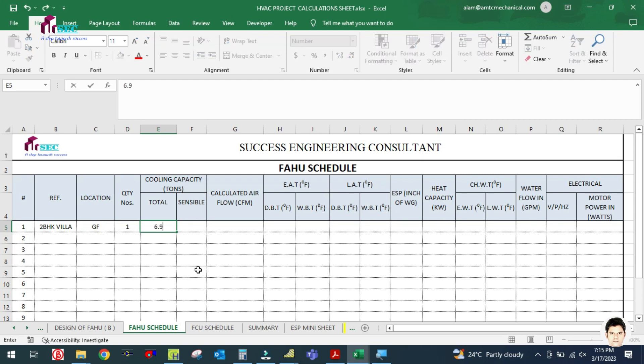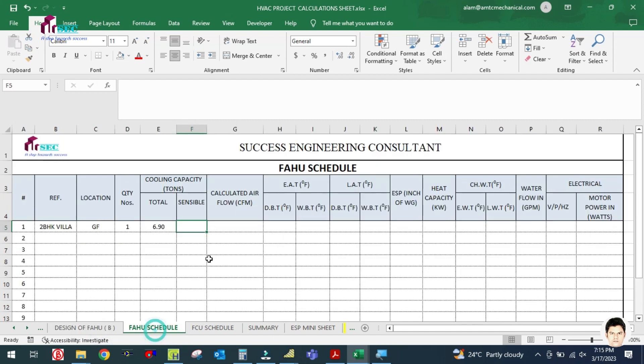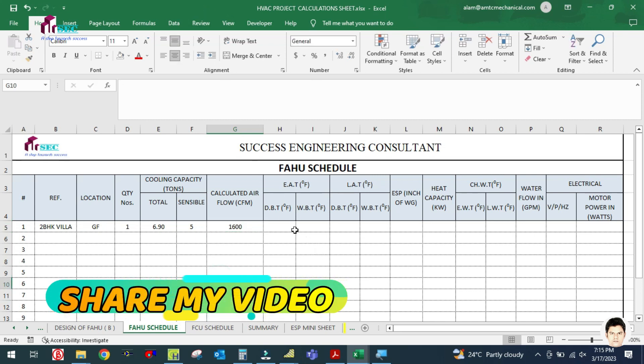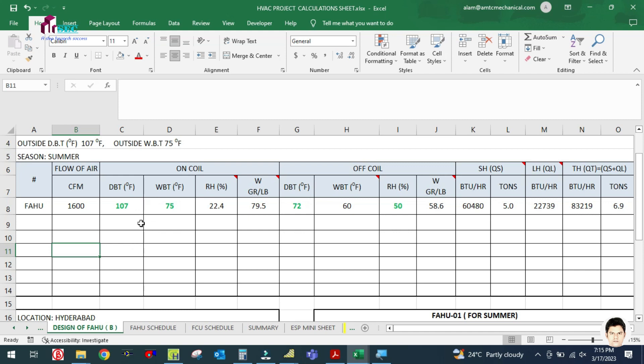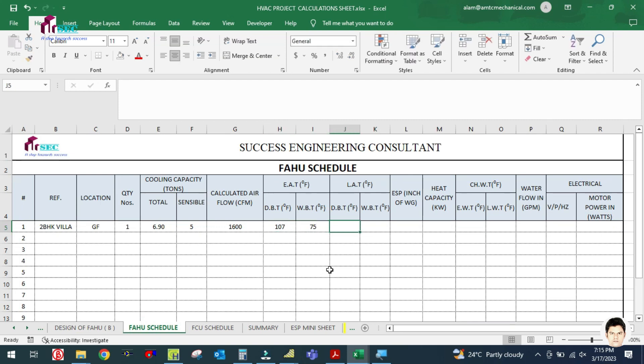The total cooling capacity is 6.9 tons and the sensible cooling capacity is 5 tons. The calculated fresh air is 1,600 CFM. The on-coil temperature is 107°F dry bulb and 75°F wet bulb.